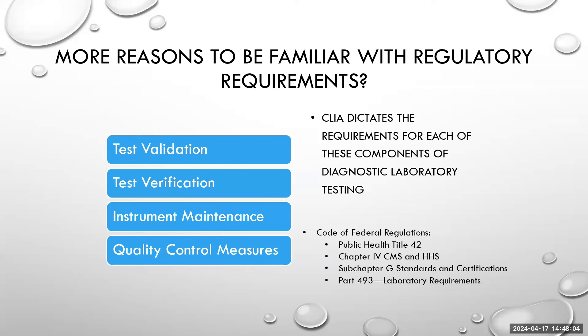We are going to discuss verification and validation and why they're important. If you're doing training with a vendor or instrument manufacturer, you want to make sure you get those maintenance records because you have to show to CAP and CLIA that you are staying within the guidelines that the manufacturer provided, so that your instrument is well cared for and providing accurate results.